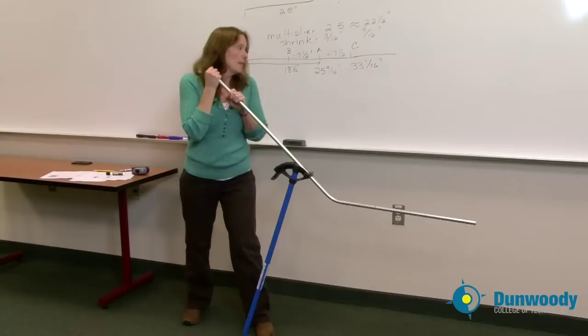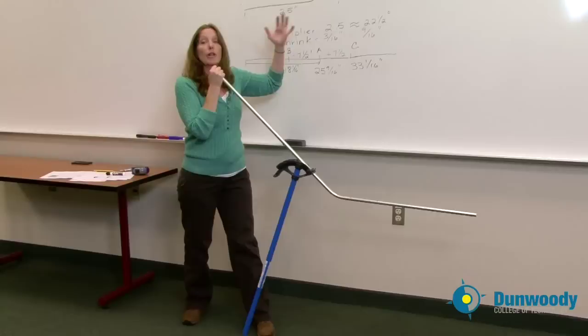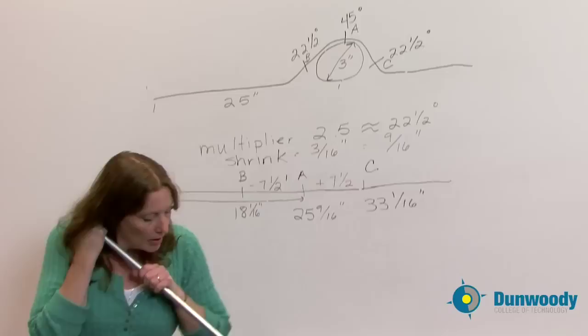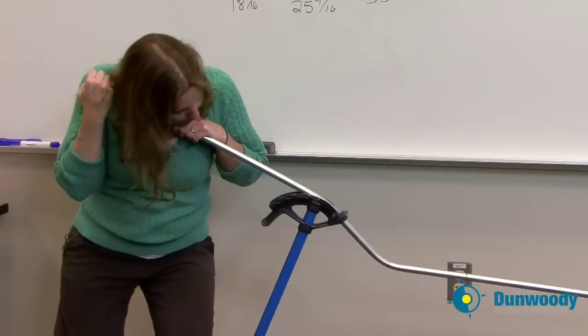Only this time I'm going to bend it, if we pay attention to what we are doing, 22 and a half degrees. We're not going to bend it at that 45. We're going to actually match up to our 22 and a half degree mark on our bender. Bend it down and go to my 22 and a half degree bend.